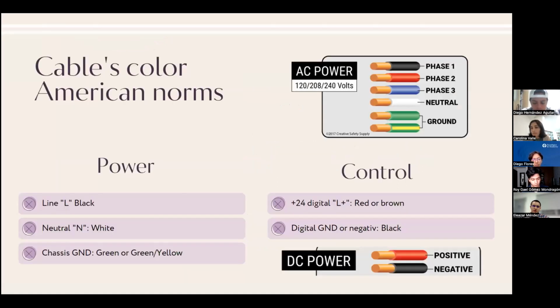First in the theory is the color norms, and we separate them in two. For the one line power, the line L is connected with black, neutral with white, and chassis with green or green-yellow cables. The control side of the panel is connected with digital positive, red or brown, and digital negative or ground with black cable.